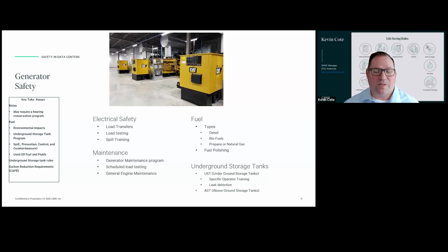With that also comes a lot of fuel. So anywhere from 30,000 to 60,000 gallons of fuel. Generally, depending on the location of the data center determines how much time they'd have on generator before they have to be refueled. So if you're in an area that has hurricanes or those types of things, and in the past it's taken X amount of time, I'm just using 48 hours or 72 hours, you'll be able to run full generator. That would be the expected load capacity, and that'd be the expected fuel amount that you'd have on site.